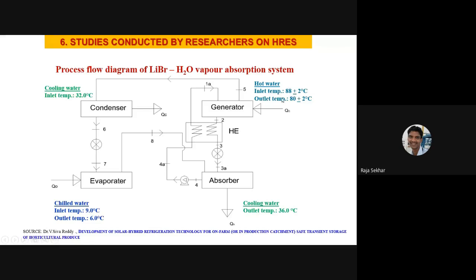The cooling water inlet temperature may be closer to your ambient, which is about 32 degrees. At the evaporator, the chilled water inlet temperature is 9 degrees and the outlet is 6 degrees, a 3 degree drop. At the absorber, the cooling water outlet temperature is about 36 degrees.